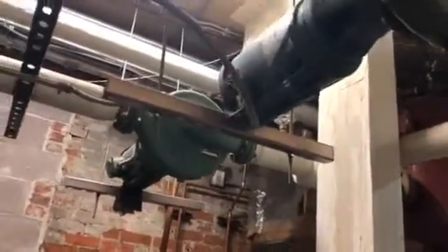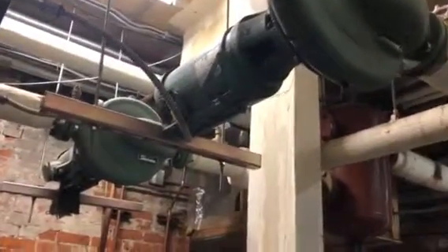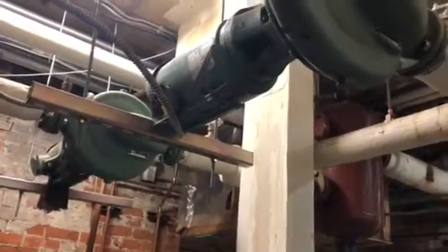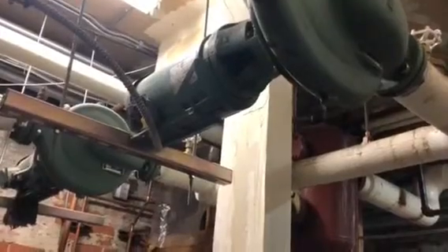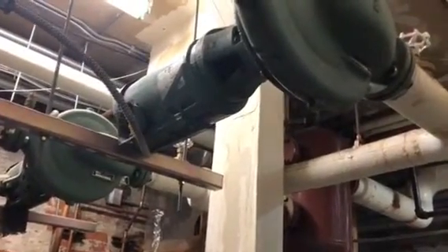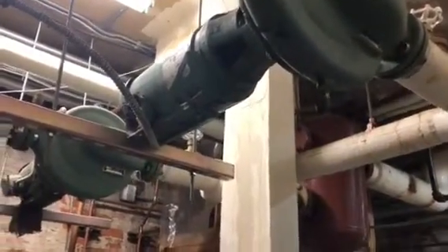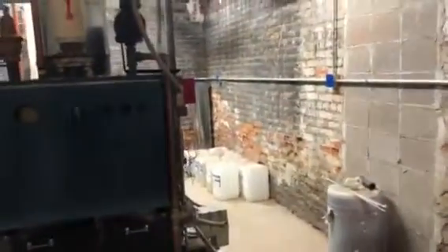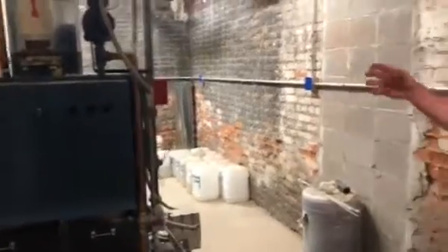One pump will run until it drops below 40 degrees outside, and then the second, maybe 30 degrees, I can check on that. But we'll turn on the second pump after it gets below a certain temperature outside. Boilers, we are staging. There are 2 stages per boiler. So we have a low and high fire. So we have 4 different stages.